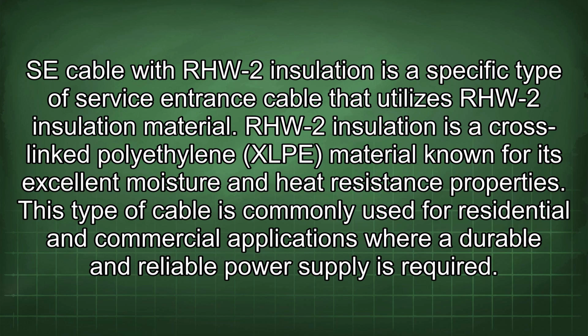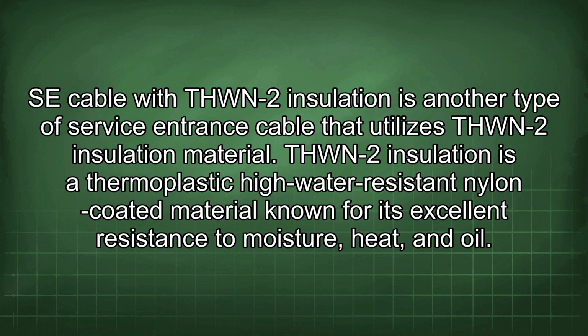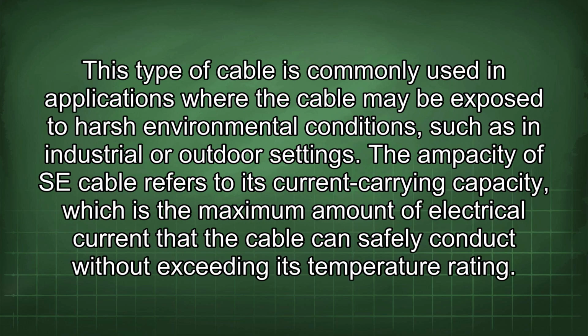insulation material. RHW-2 insulation is a cross-linked polyethylene (XLPE) material known for its excellent moisture and heat resistance properties. This type of cable is commonly used for residential and commercial applications where a durable and reliable power supply is required. SE cable with THWN-2 insulation is another type of service entrance cable that utilizes THWN-2 insulation material. THWN-2 insulation is a thermoplastic high-water resistant nylon-coated material known for its excellent resistance to moisture, heat, and oil. This type of cable is commonly used in applications where the cable may be exposed to harsh environmental conditions, such as in industrial or outdoor settings.